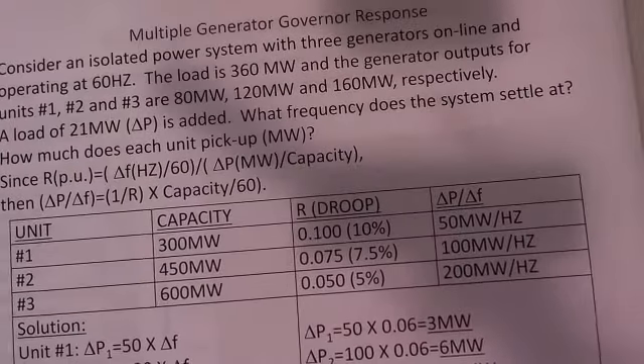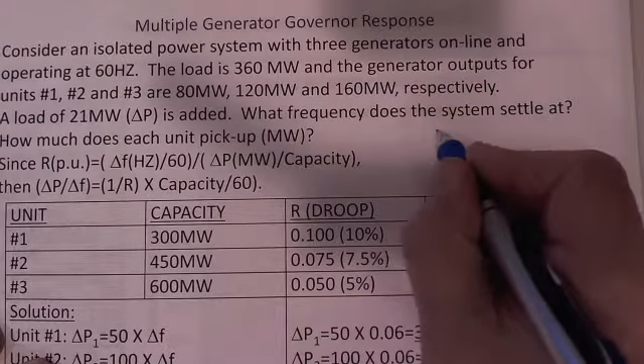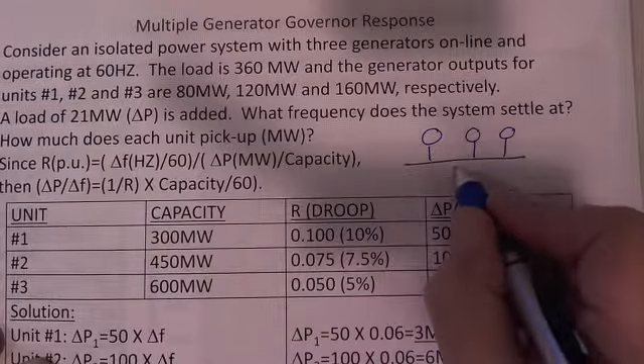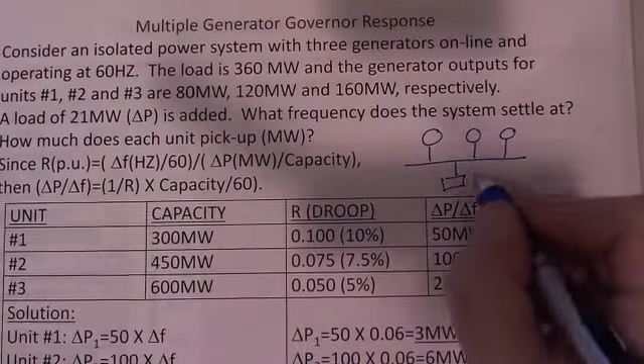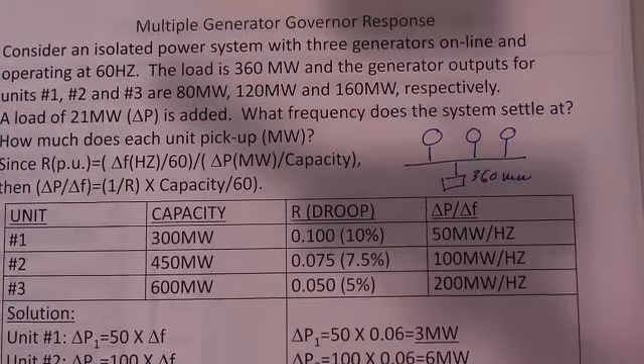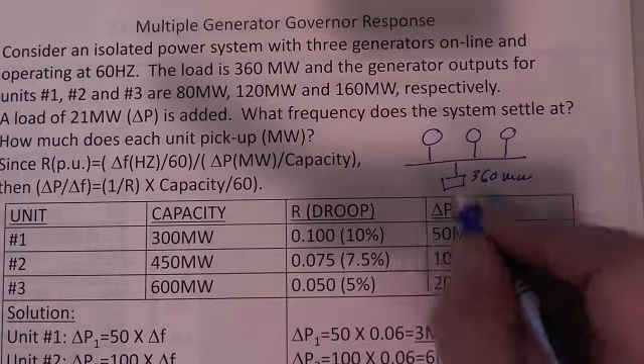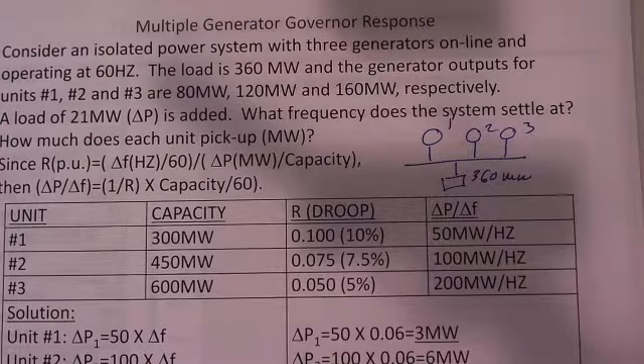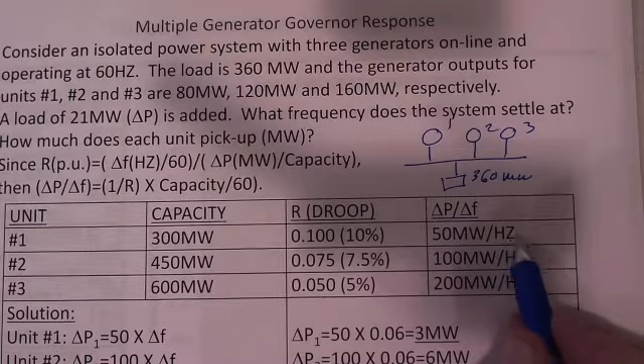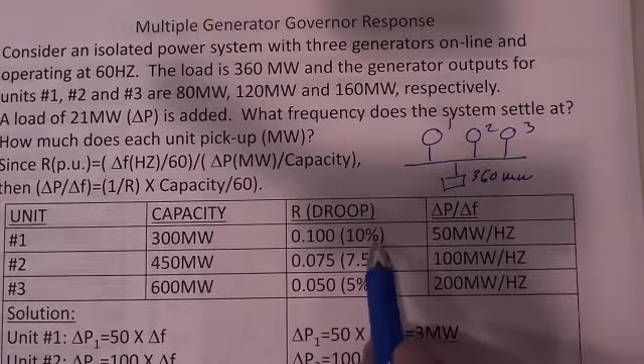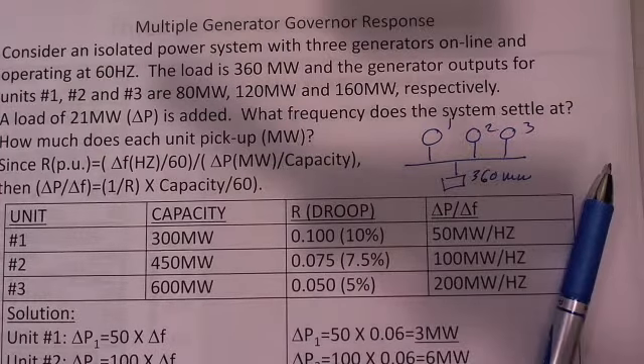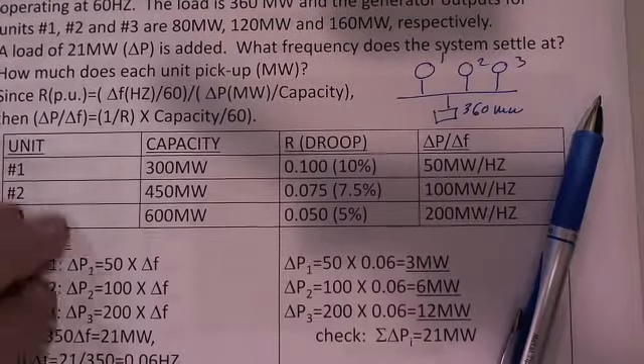here's an example. He's got an example. He's got three generators. He's got a load, and he says he's supplying 360 megawatts here. He's got different droop characteristics, or this is 1, 2, and 3. He's got different droop characteristics. So there they are here. How many megawatts per hertz, if you will, in there? But it's usually expressed as a percentage. Much of the time, you will see this as a percentage on the base, where the base is the capacity of the generating unit. So you have to convert the numbers to get them to a common base in order to do the problem.